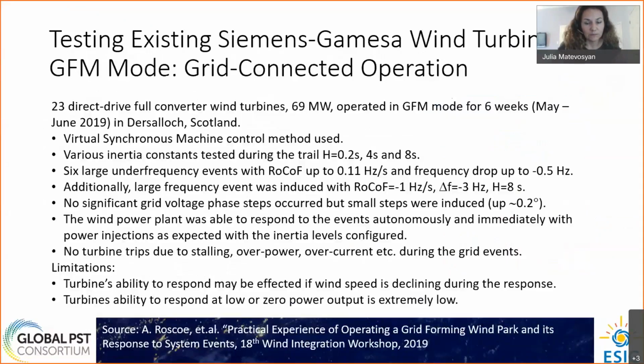This project is where grid-forming control was applied in 23 direct drive full converter wind turbines, a 69 megawatt wind farm. The wind farm is an existing wind farm. It was designed as a grid-following wind farm initially, but its controls were modified and it was tested in grid-forming mode for 6 weeks in 2019. There, a virtual synchronous machine control method is used. Virtual inertia constants that were tested during the trial were from 0.2 seconds to 8 seconds.